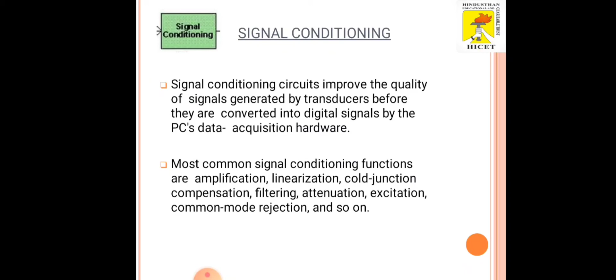The input signal received from the transducer is actually very low, so it has to be converted into readable data. Then linearization, which is aligning the signals, and cold junction compensation, filtering, attenuation, excitation, common mode rejection, and so on. These are the common functions of signal conditioning, and it is the most important stage. At this level, the signal is improved for future purposes.